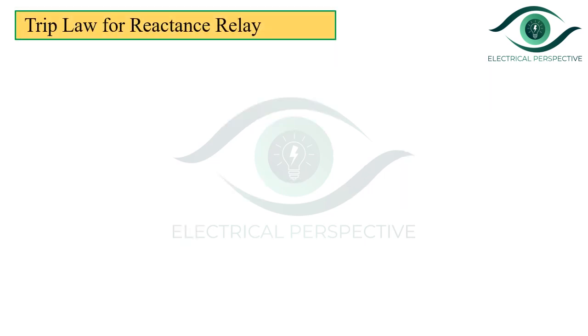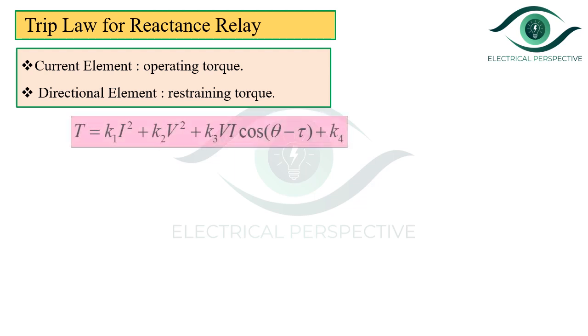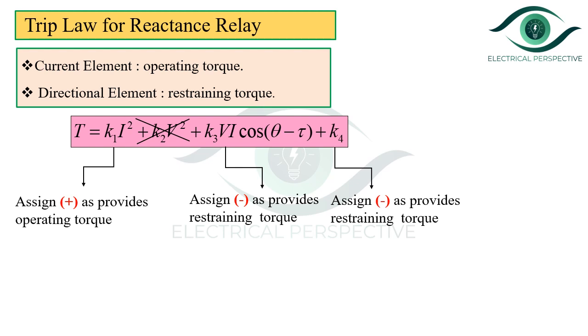Now let us derive the trip law for the reactance relay. The current element provides the operating torque and the directional element provides the restraining torque. Rewriting the universal torque equation: the current element provides operating torque, so we assign a positive sign to K1·I². There is no role of the voltage element, so K2·V² = 0. The directional element provides restraining torque, so we assign a negative sign to K3·VI·cos(θ − τ).